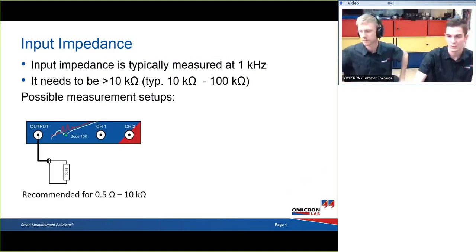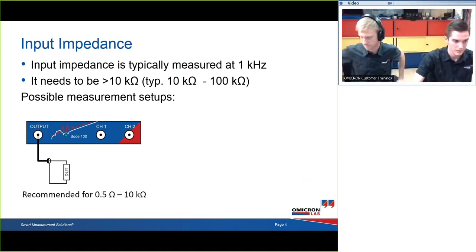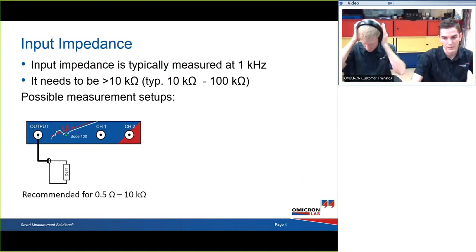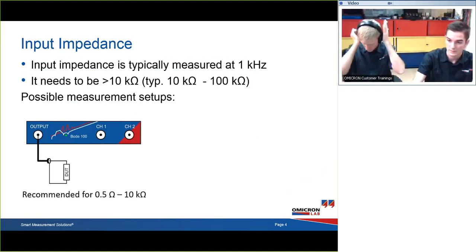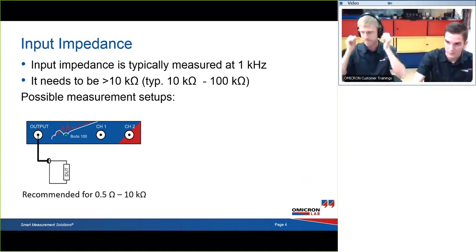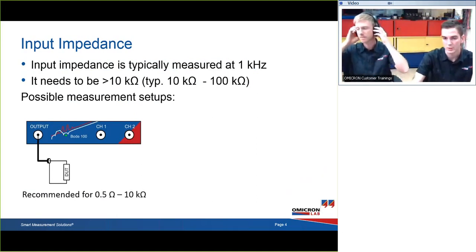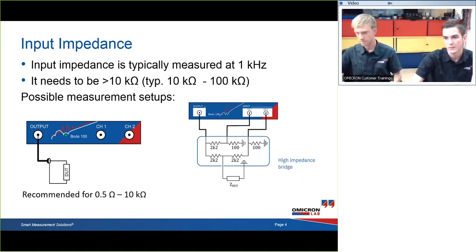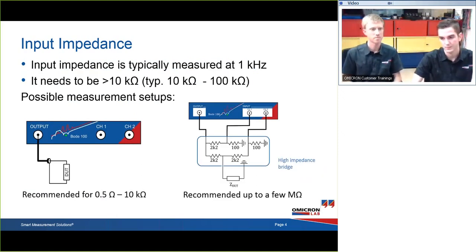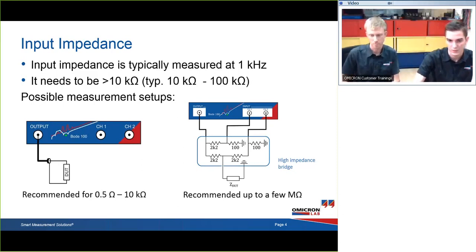There are two possible measurement setups. On one hand, there's the one-port measurement, which is recommended for impedances from 0.5 Ω to 10 kΩ, maybe 20 kΩ. So if your impedance reaches 100 kΩ, you have to use a high-impedance bridge, which can measure up to a few megaohm impedances.